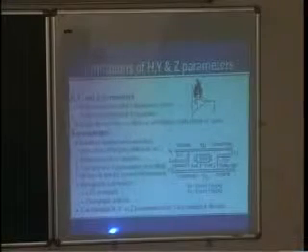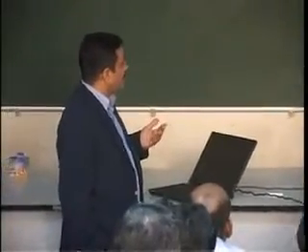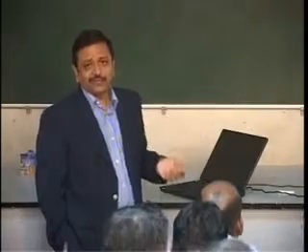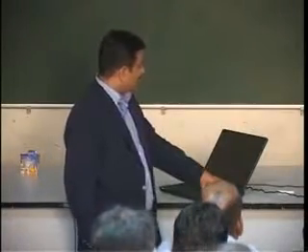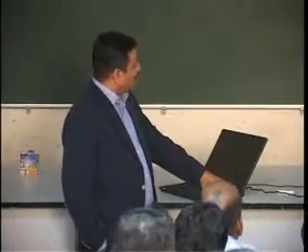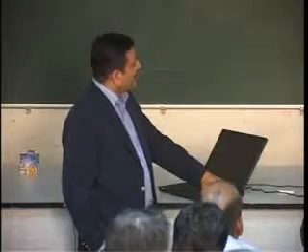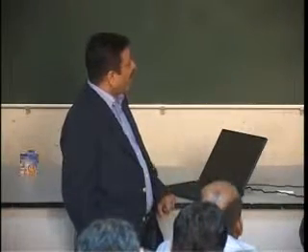And even if you put a probe or a detector on any micro device, its own inductance and its own capacitance will affect the performance. So generally the S parameter is the only way where we can measure the gain, loss, and reflection coefficient of a device.